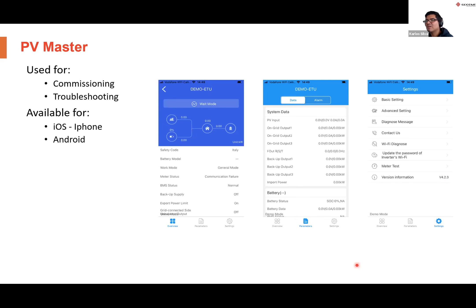In terms of the work modes, we do have 3 unique work modes. We have the general work mode, which is the standard logic of operation. So this is the mode that is used to increase your self-consumption. So that means that the PV power is used to power the loads, then charge the batteries, and then export into the grid. We do have an economical mode, which is generally used for customers who are on a time of use tariff. So this allows you to set programmable schedules for charge and discharge regimes into 4 groups. These are repeatable in terms of daily and weekly. As I mentioned, they are ideal for time of use tariffs.